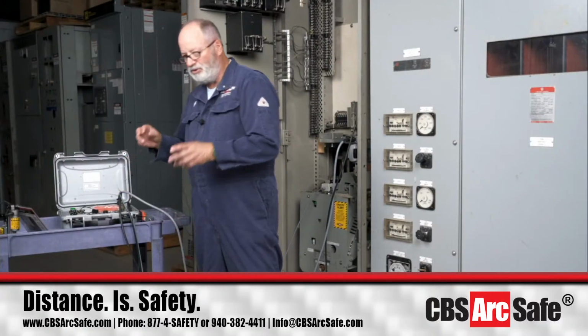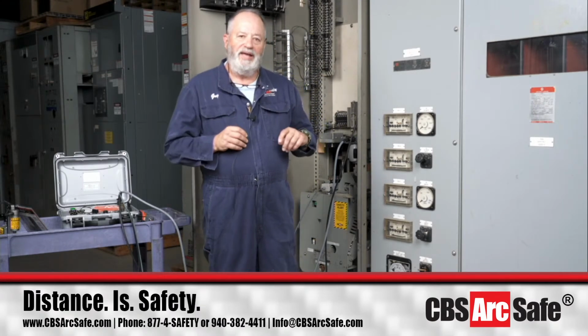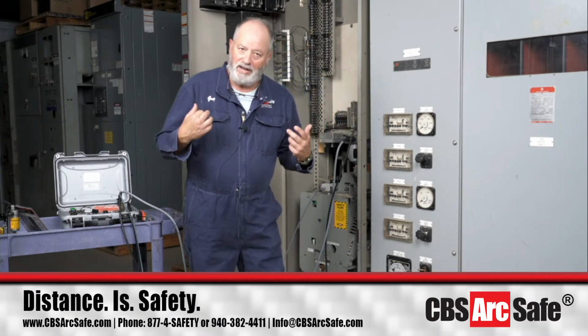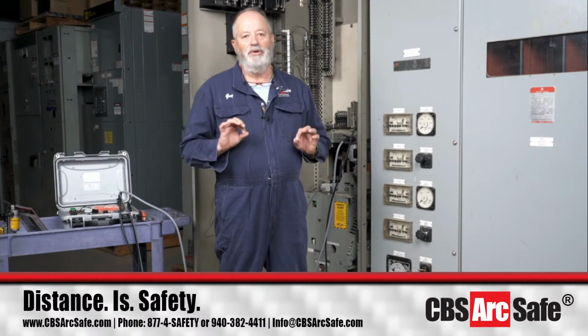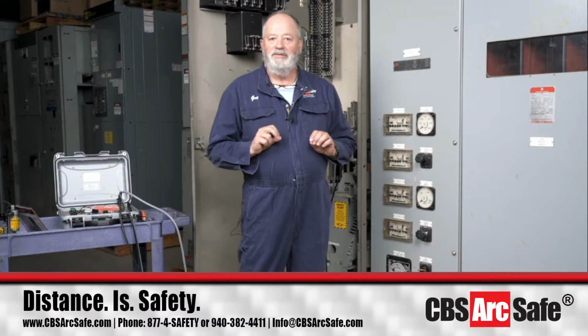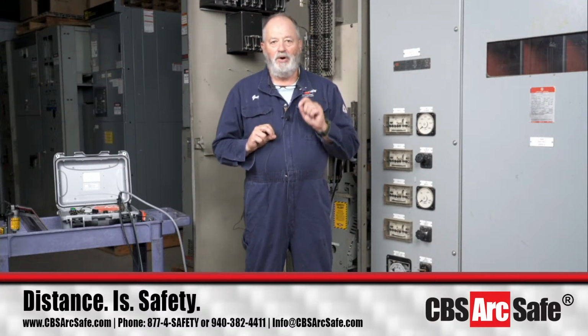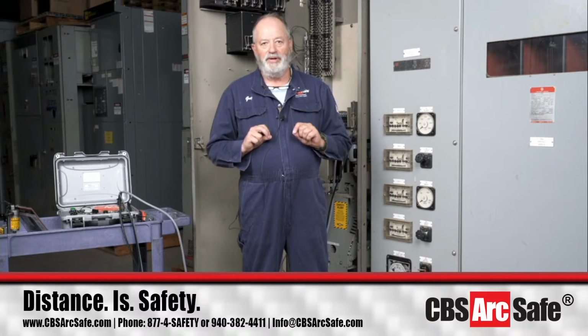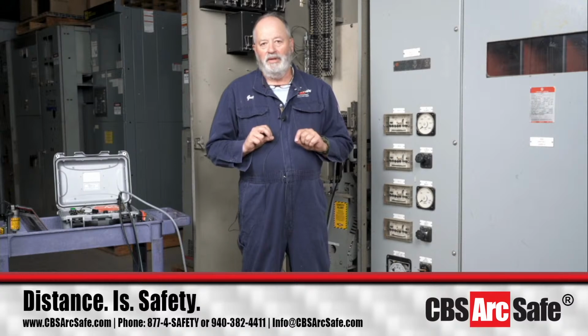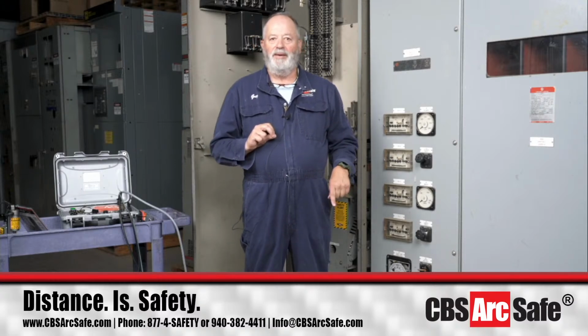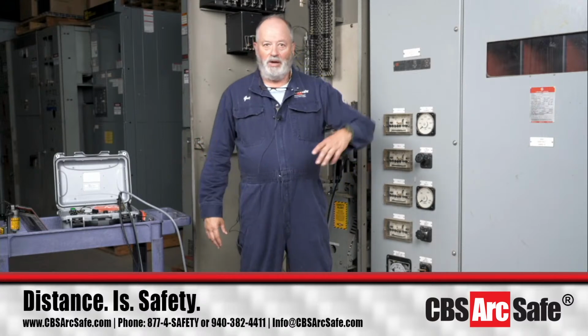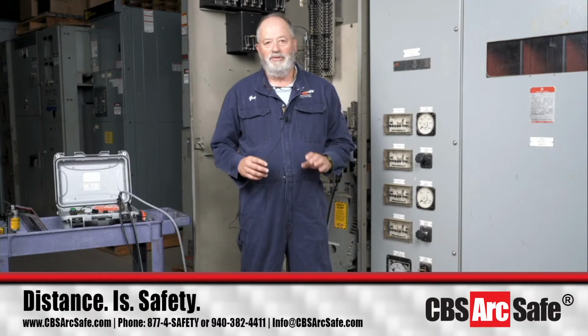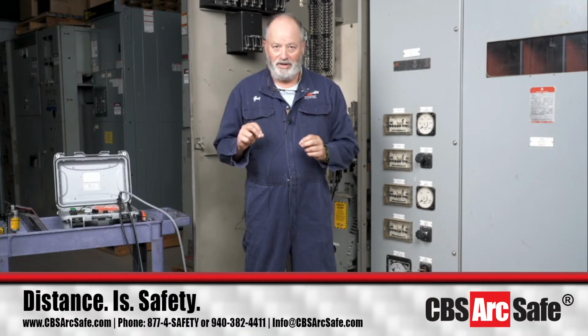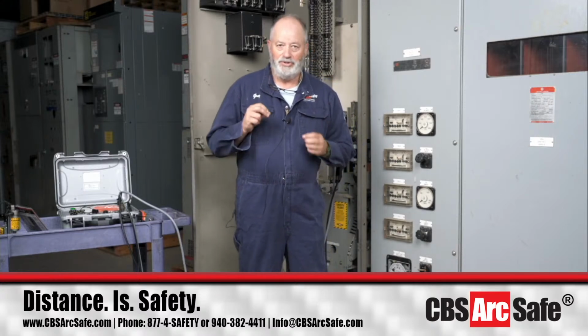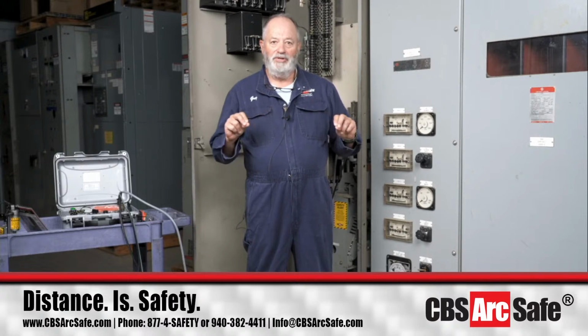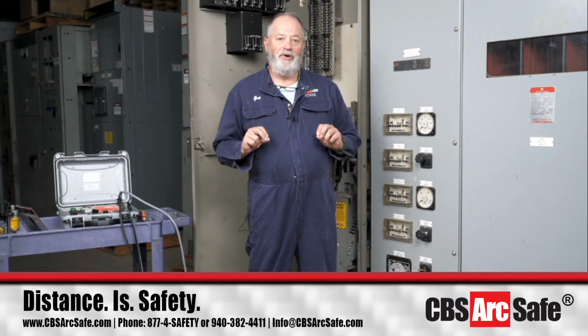And the reason we came up with the tilt switch is this: many times people have had Magne-Blast switchgear over time, and if they haven't been doing proper maintenance on the cubicles, it can slip a gear. Our chief scientist and CEO said he always wants the operator who's installing or removing the breaker to have full control over that operation. He can be alerted and work to select the opposite direction. It's not an automatic feature where the thing stops itself when the tilt switch goes off. It's up to the operator to know the tilt switch has gone off and to stop the operation and reverse it, or simply stop it, based on what standard operating procedure the company decides.